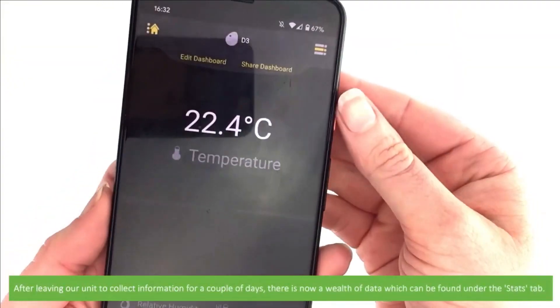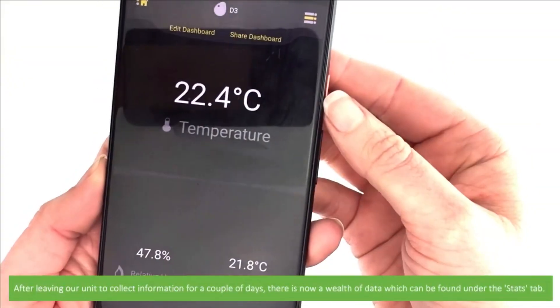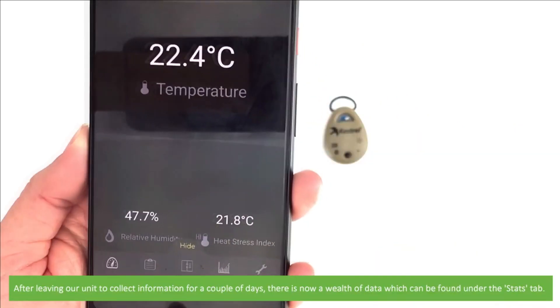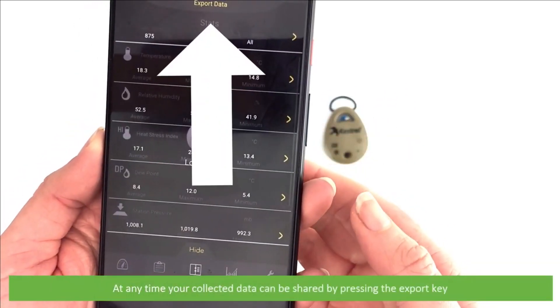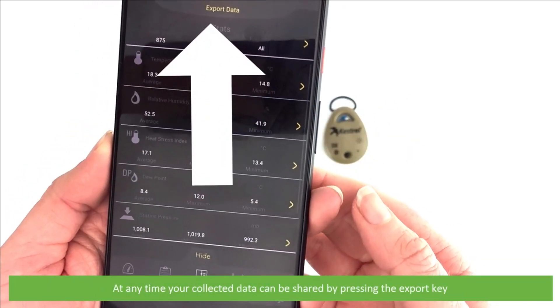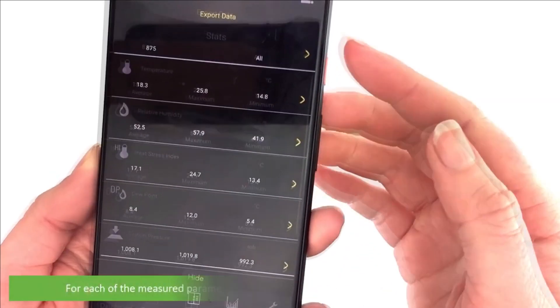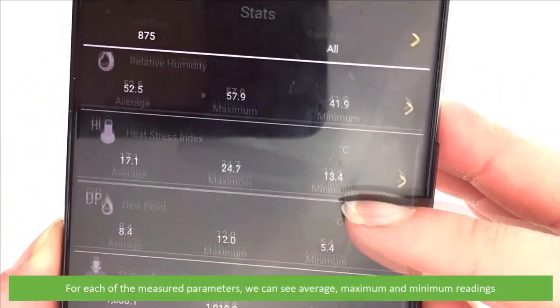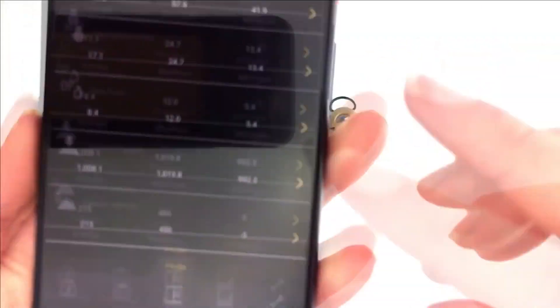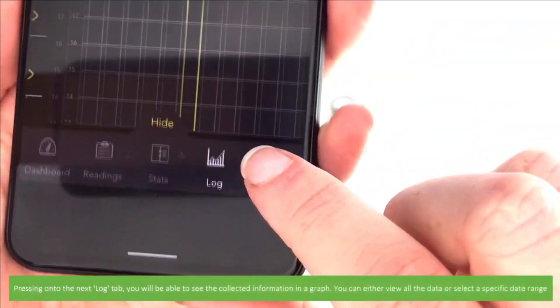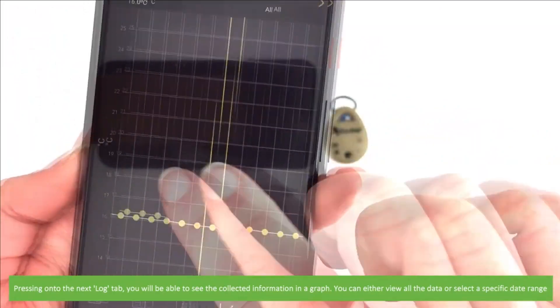After leaving our unit to collect information for a couple of days, there is now a wealth of data which can be found under the Stats tab. At any time your collected data can be shared by pressing the export key. For each of the measured parameters we can see average, maximum and minimum readings. Pressing onto the Log tab you will be able to see the collected information in a graph, and you can either view all of the data or select a specific date range.